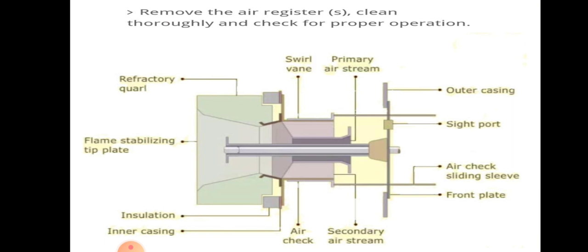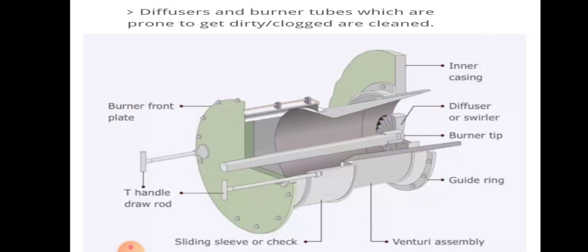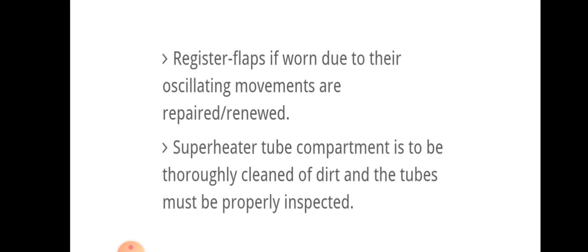Remove the air register, clean it thoroughly and check for proper operation. Then the diffuser and burner tubes, which are prone to get dirty or clogged, are cleaned. Register flaps, if worn due to their oscillating movements, should be repaired or renewed.